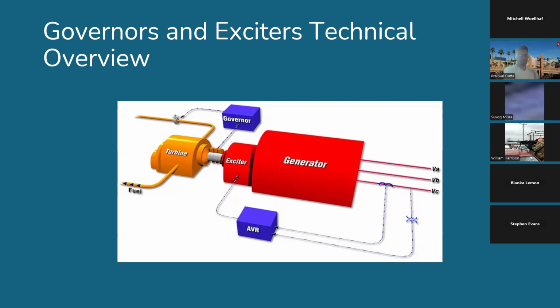Two important operational modes are ISO mode and droop mode. In ISO mode, the generator maintains a fixed frequency regardless of load changes, making it ideal for islanded microgrid operation, where the generator is the only source supplying the loads. Droop mode, on the other hand, allows the generator to adjust its frequency slightly in response to load variations, ensuring that multiple generators share the load without competing against each other.